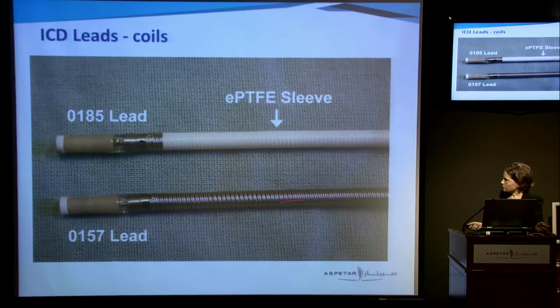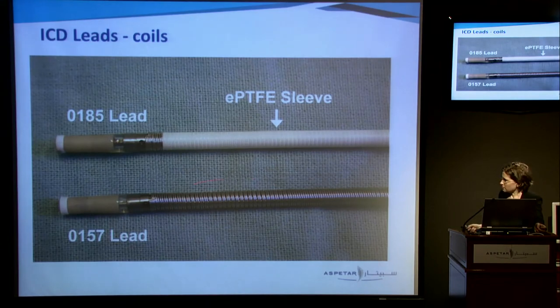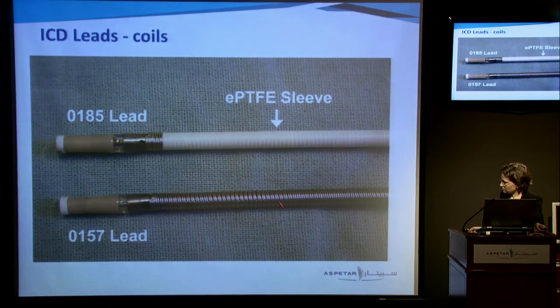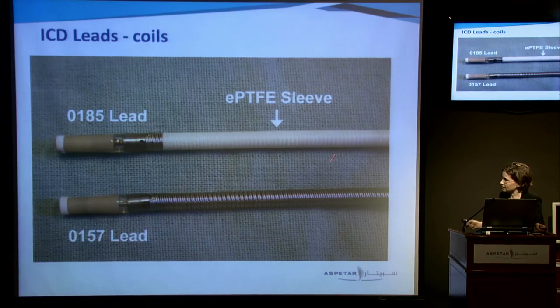One of the problems with the coil is that when it's been implanted in the heart for more than six months, the endocardium starts to grow over the lead and can invaginate into the coil itself. This is a big problem if we have to extract the lead — it makes extraction very difficult. One thing manufacturers have started to do is coat the coils completely in Gore-Tex to try to make them easier to extract.